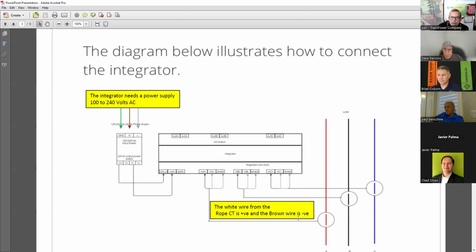So this is the part we were talking about, as to how important it is that you get the brown connected to brown, orange connected to orange, yellow connected to yellow. And then positive, negative is very important here. And then one more thing I didn't mention about the CT is you need 100 to 240 volts power. So you need a 120 volt power, positive, negative, and a ground to be connected here: line, neutral, and ground, to the integrator kit.